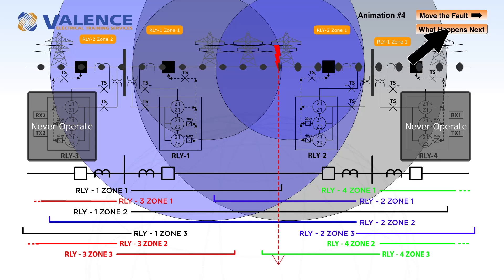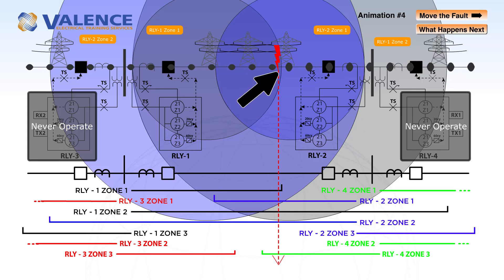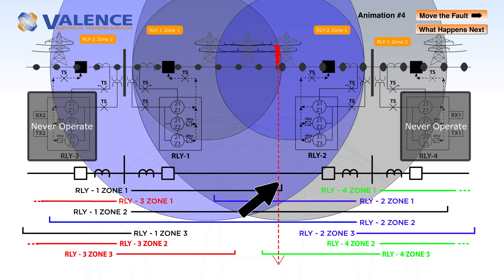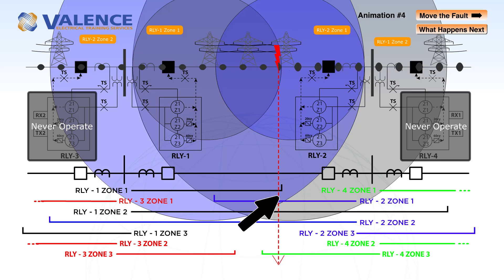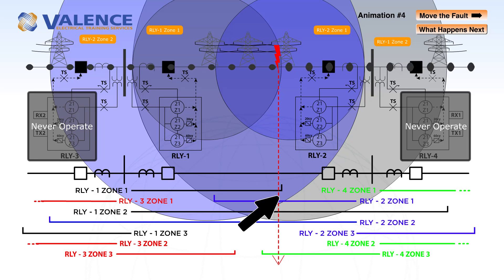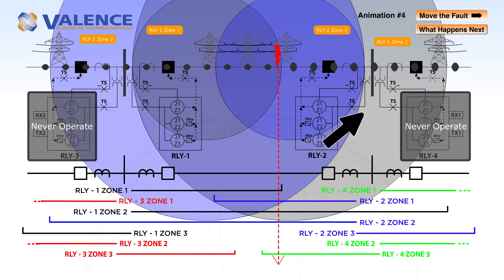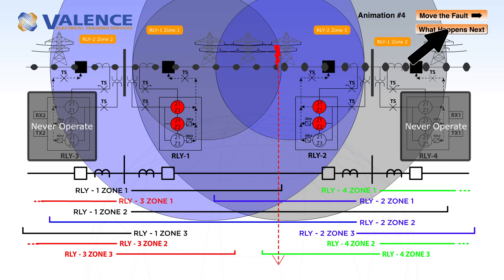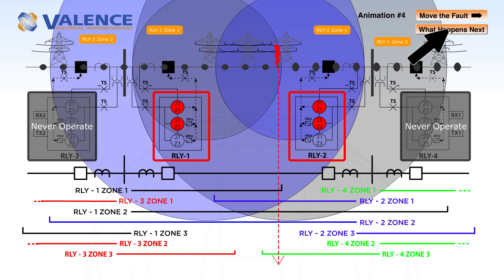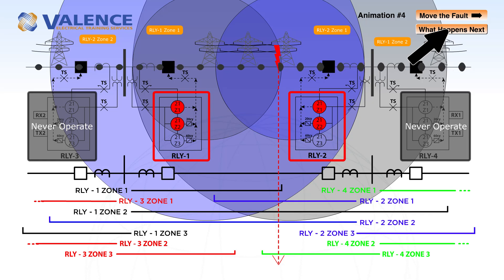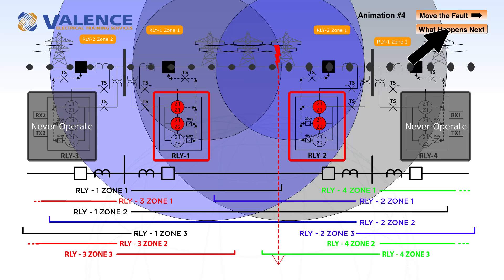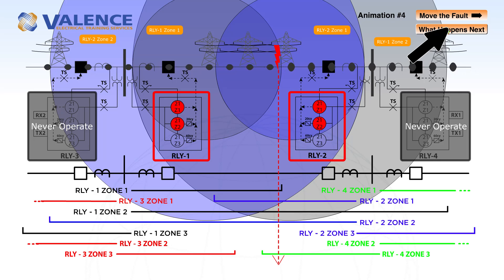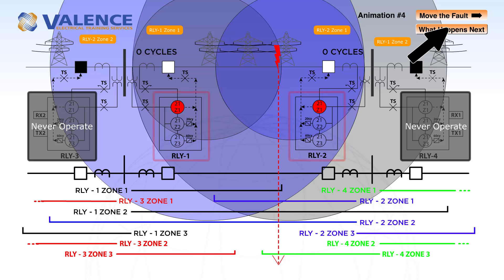If we move the fault closer to relay 2, you can see that, again, we're in the overlapping region between zone 1 and zone 2. This means that both relays will detect a zone 1 and zone 2 pickup. Zone 1 has no intentional time delay, so both relays operate instantaneously.